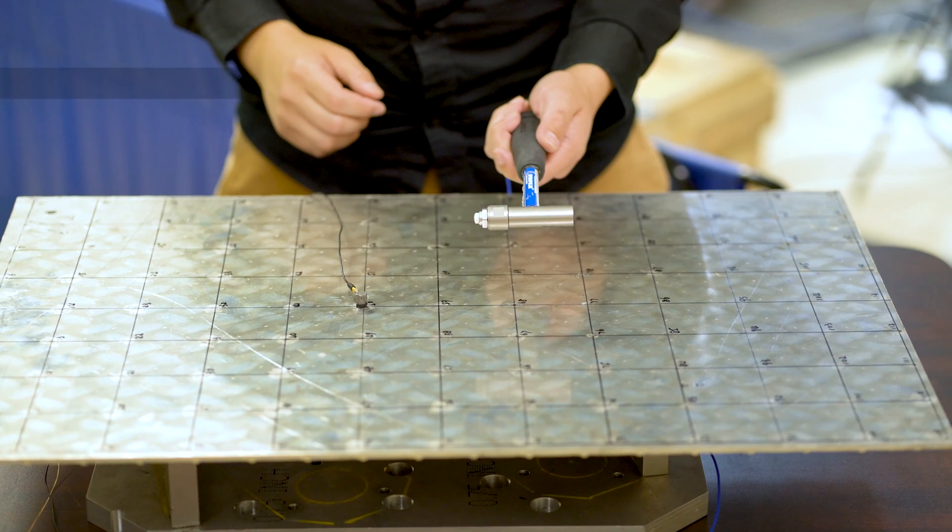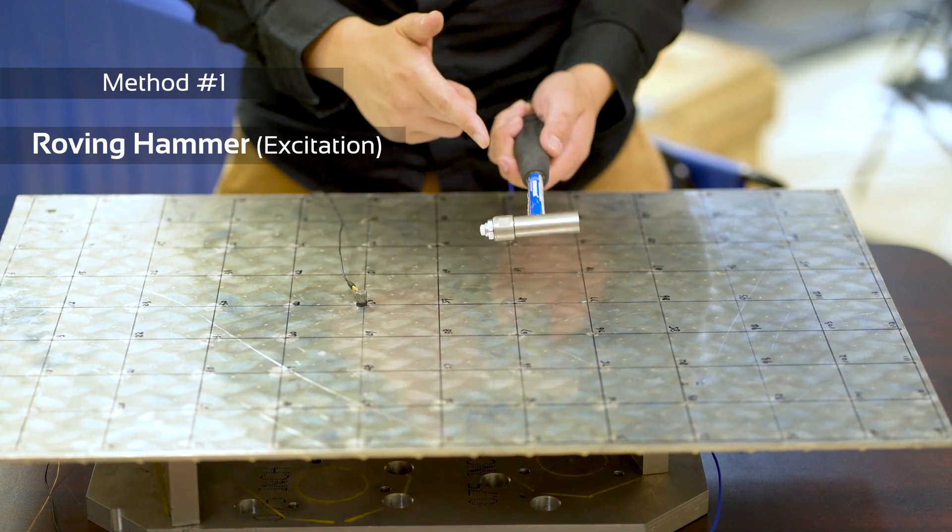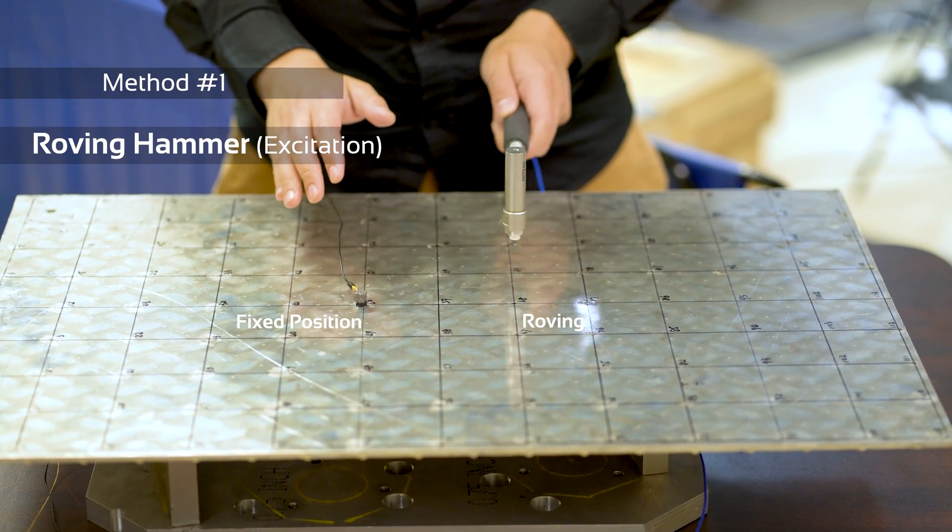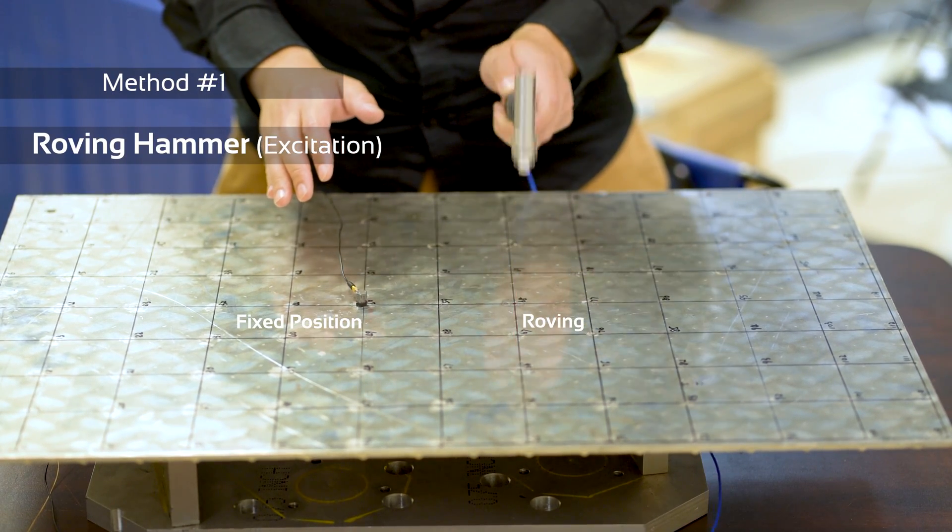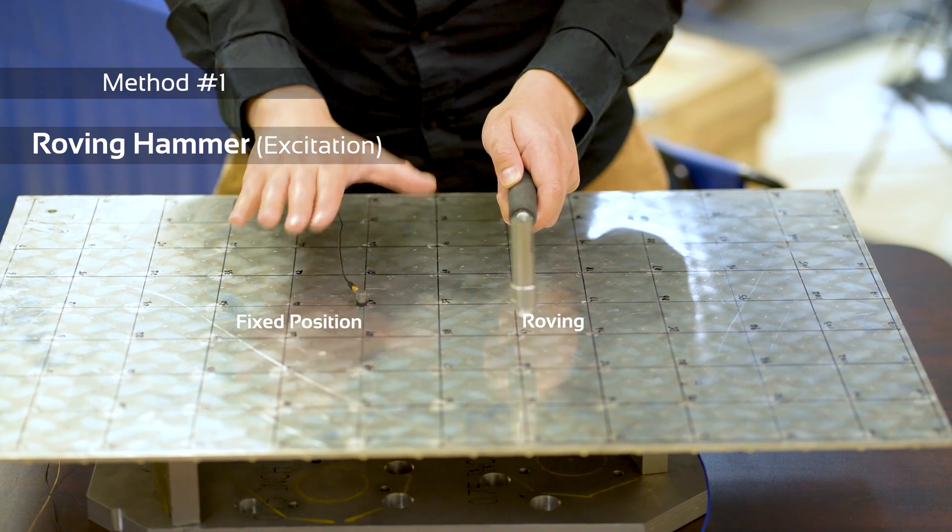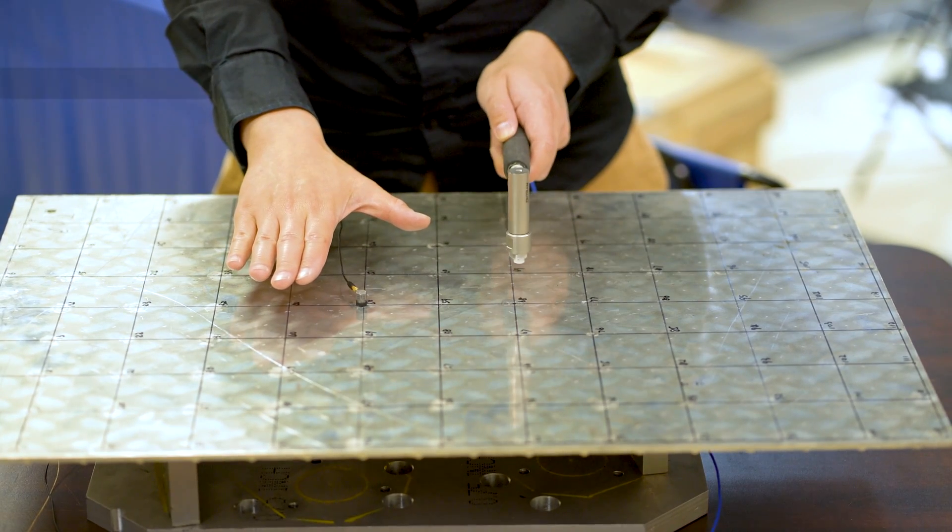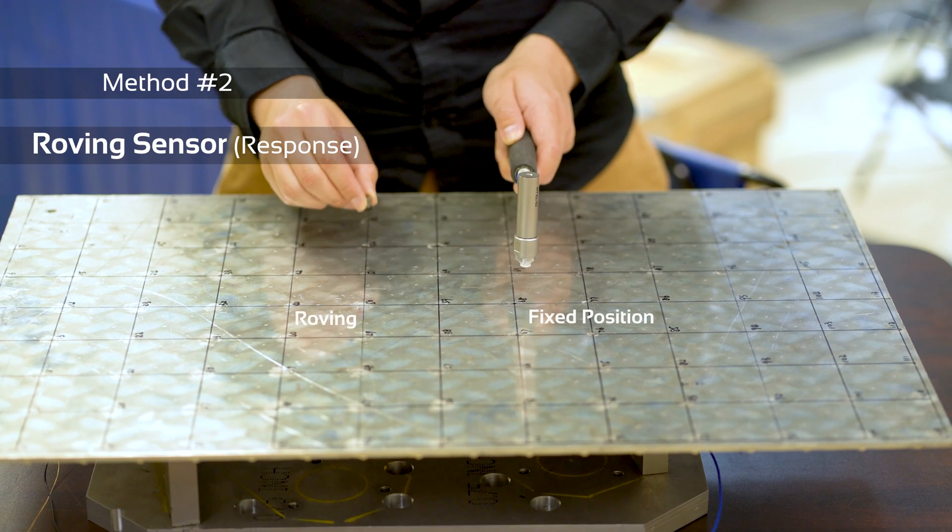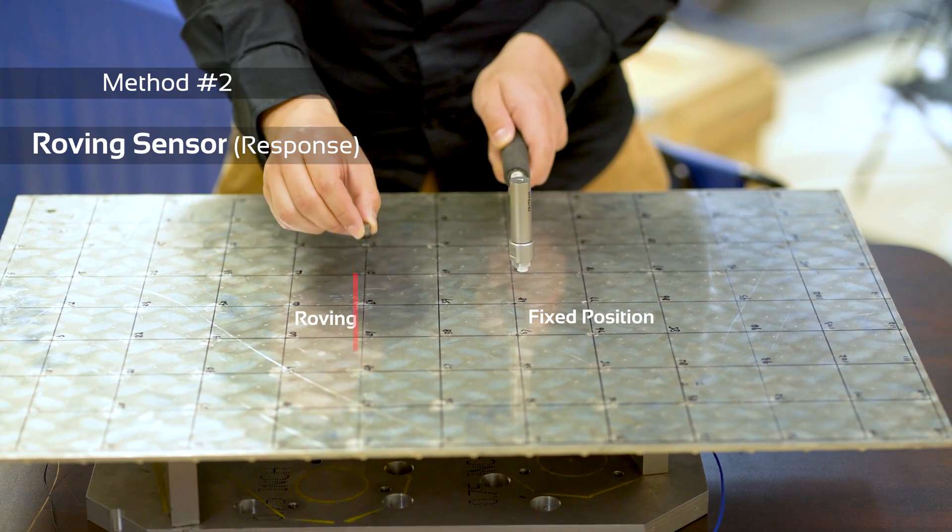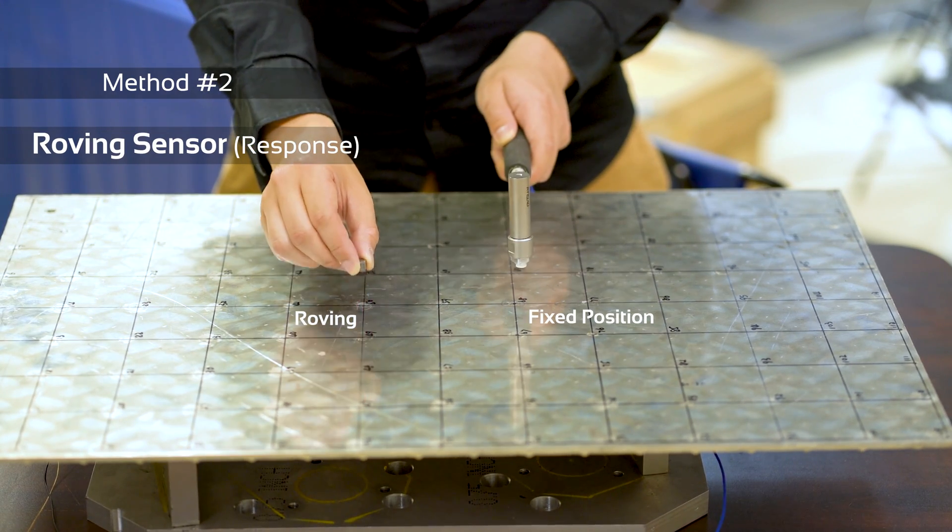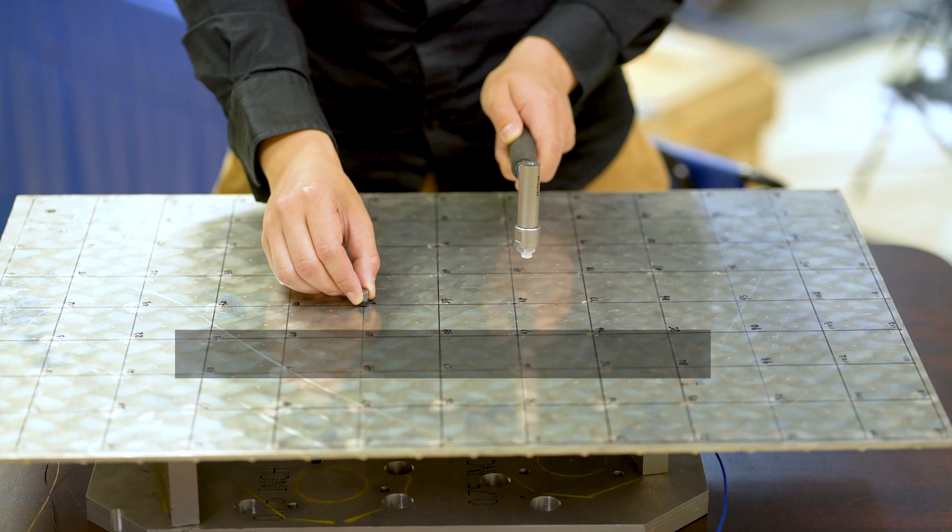The first method is the roving hammer method in which you use a modal hammer to excite the structure at various measurement points. The response points are fixed. The second method is the roving response method in which the excitation points are now fixed but the responses are measured at several points. For this video I will demonstrate the roving excitation method.